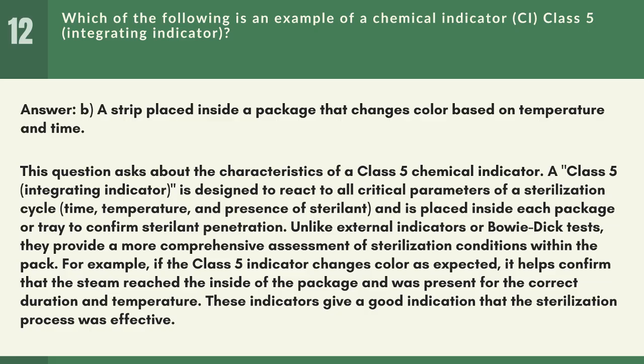For example, if the Class 5 indicator changes color as expected, it helps confirm that the steam reached the inside of the package and was present for the correct duration and temperature. These indicators give a good indication that the sterilization process was effective.